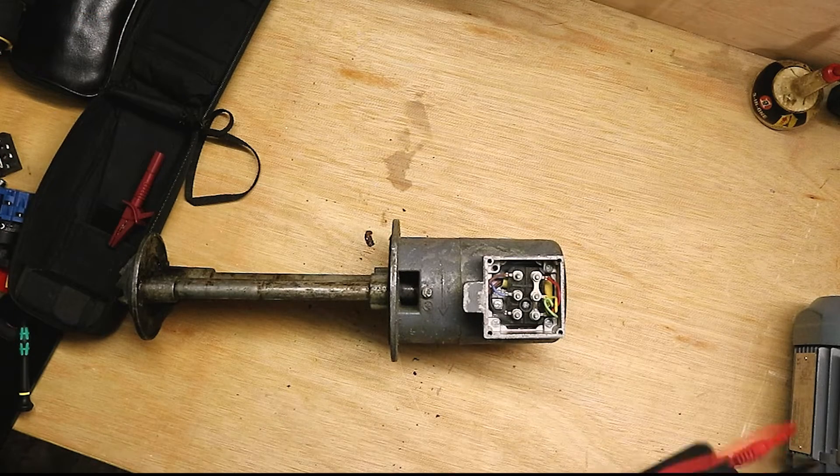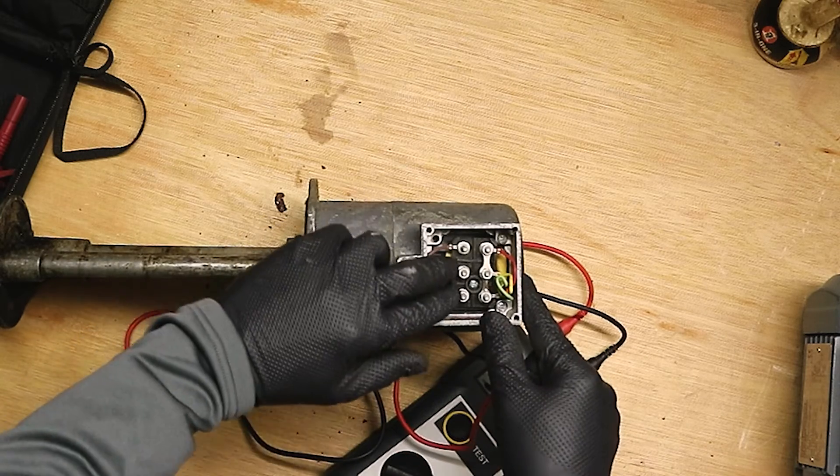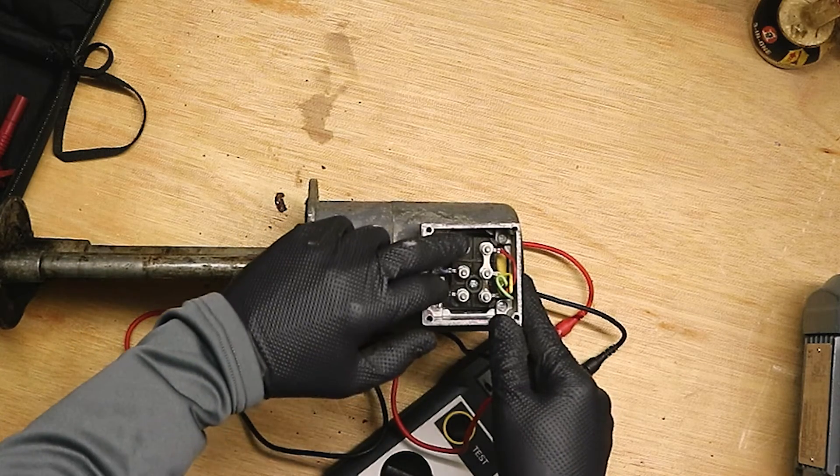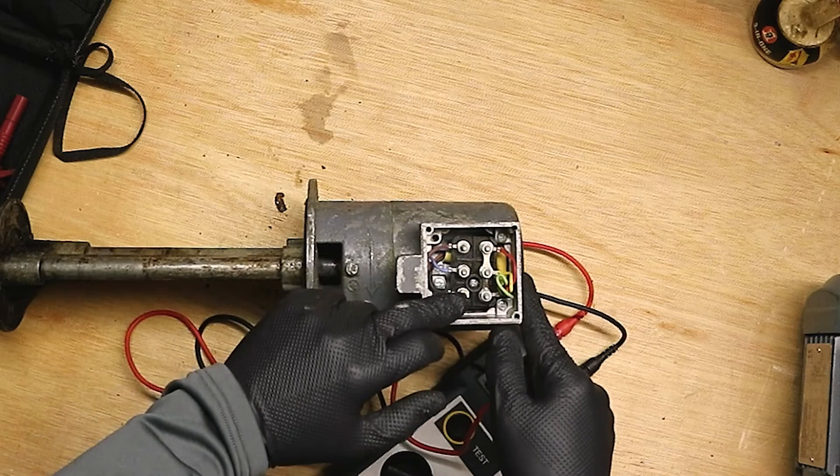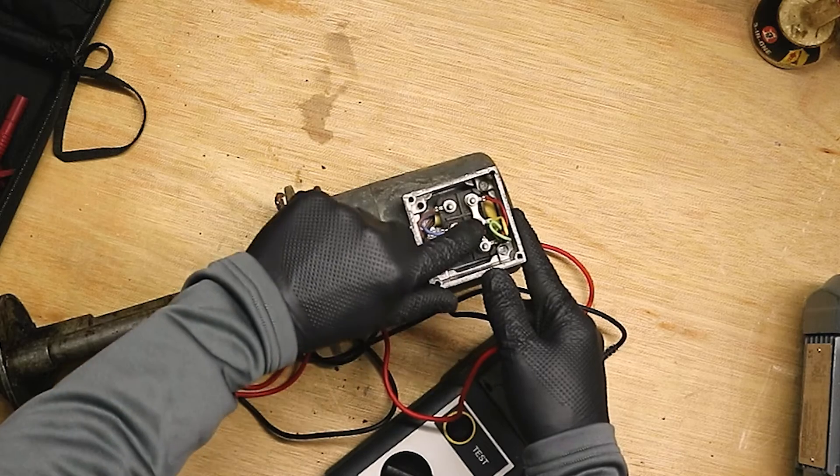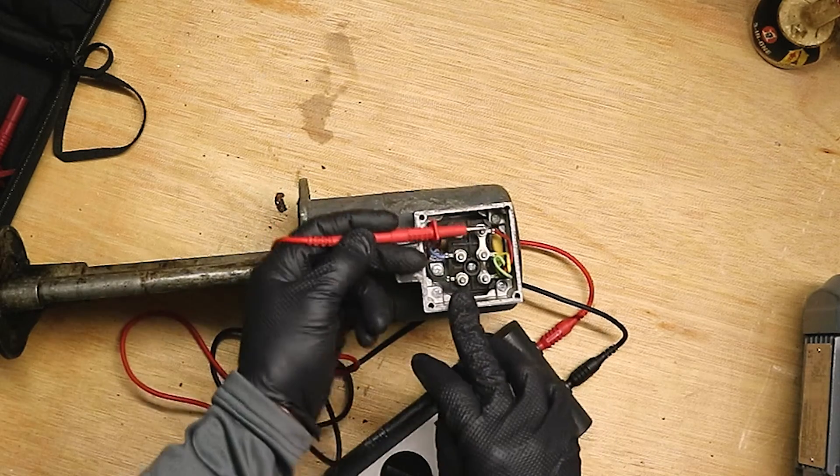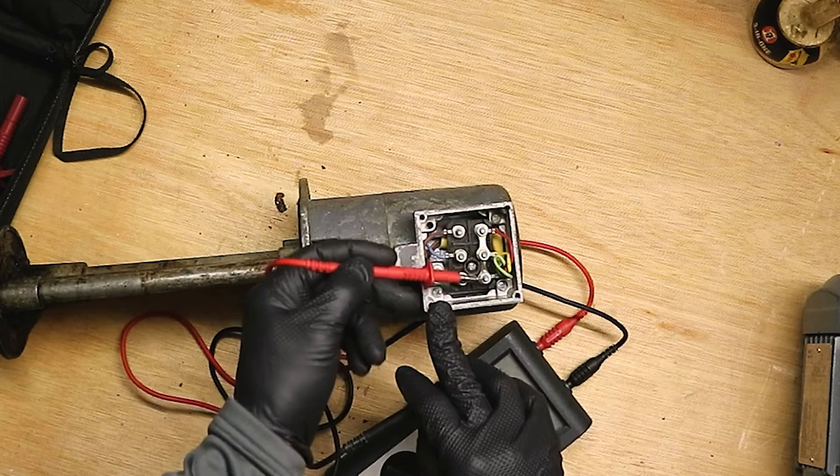So, we have the terminal cover off. You can see that this motor is connected in star, so we've got our three windings U, V and W coming back to star point and the jumpers have been connected across the star point. This one is in star, if they were long ways they would be connected in delta.